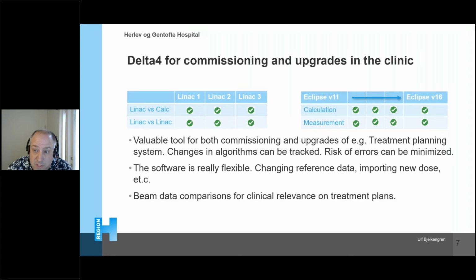Using the Delta 4 system, I would say baseline patients or baseline patient plans are calculated whenever doing new upgrades and compared to previous calculations and measurements. We can track any changes in treatment planning algorithms and of course reduce the risk of any gross errors due to the upgrade. We like the software, it's flexible. You can change the reference data, you can import new dose, you can compare to other measurements and so on. So use your imagination.